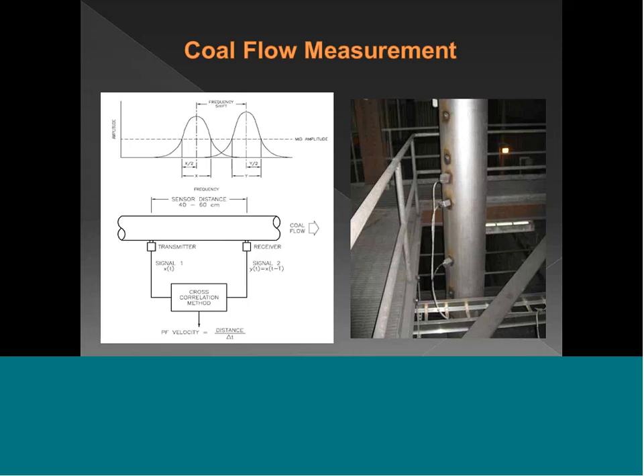The microwave measurement is simply a change in frequency. The only calibration that needs to be done to measure coal in a coal pipe is to look at this frequency spectrum when the pipe is empty, and we're going to develop this baseline or zero frequency curve. When we load the pipe with coal, the frequency shifts, and that frequency shift is dependent on the mass of what's between those two antennas, those two sensors. So that's our mass measurement. And I just want to highlight that that mass measurement is very critical that we establish this baseline zero. So we want to make sure we get that zero and that we check that zero every time a pulverizer is out.